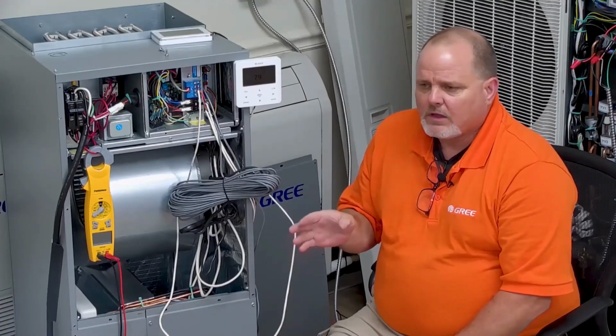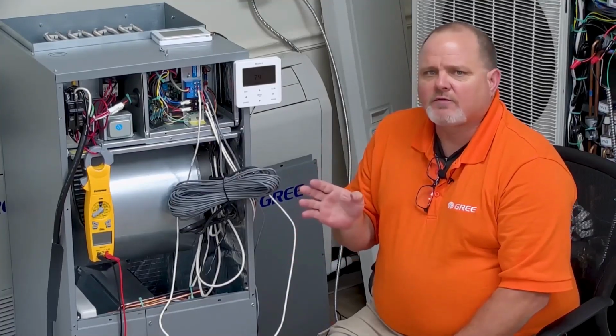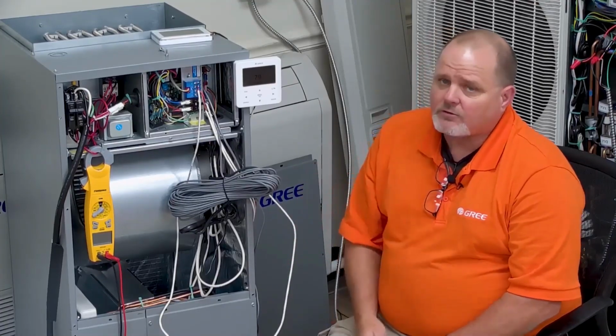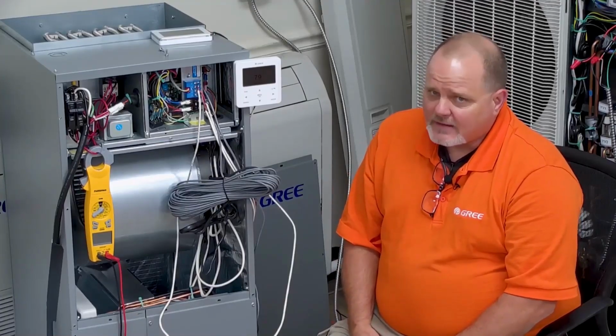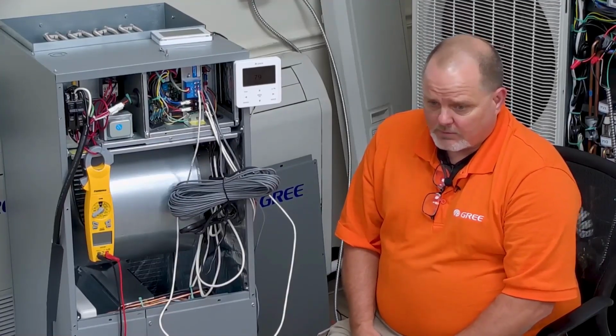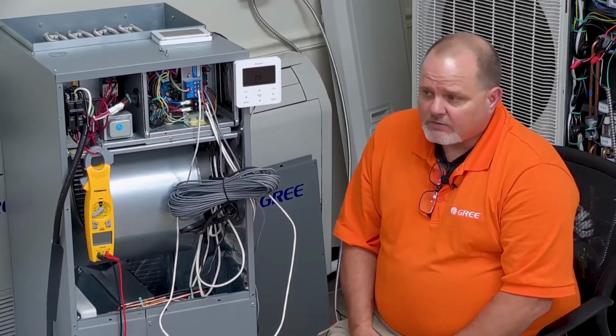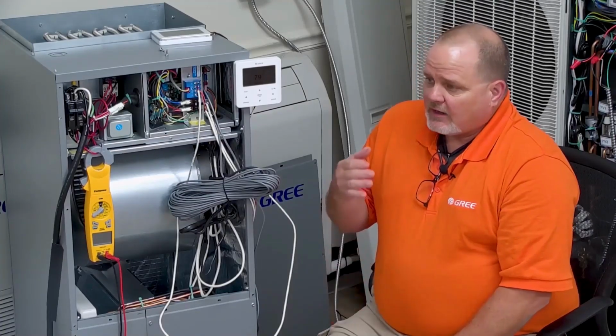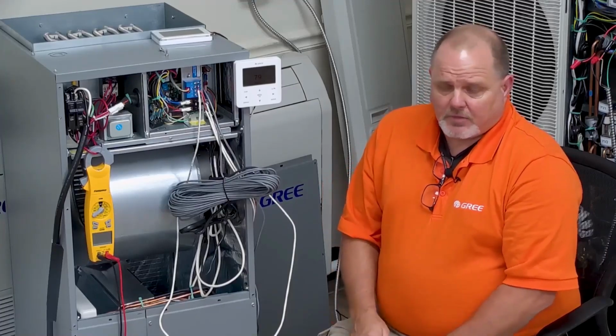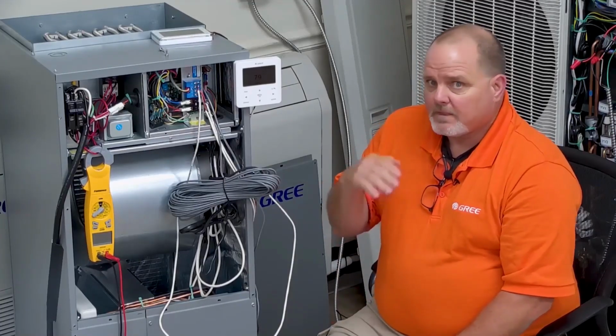It's heating the home. Let's say it gets cold enough out there, which we all know with the MultiPRO Ultra, it's got to get very cold before the heat pump's not keeping up. But even so, let's say you're up in our northern climates and we get some really sub-zero temperatures and wind chills and everything else, and the heat pump slips a little bit and it can't keep up anymore. The auxiliary heat function, exactly that. It will automatically bring on the electric heat and help the heat pump out.